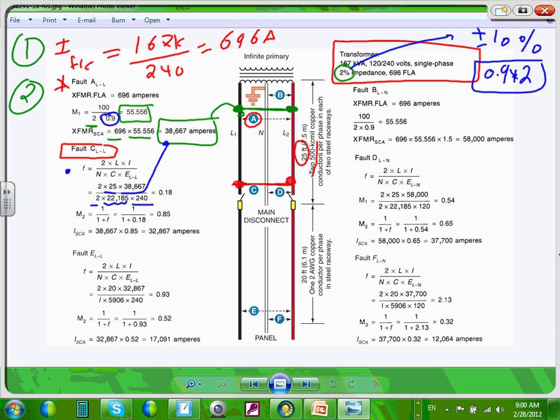If it's copper, you need to decide, is it 600 volt or higher than 600 volt? It's a 600 volt system, right? Less than 600 volt system, 240. And is it non-magnetic or steel conduit? Am I putting them in a steel conduit? Can you guys see where it says steel conduit here? Steel conduit. So do me a favor. What size conductor? 500. Can you go all the way to 500 under 600 volt steel? What's the number? 600 volt, 500 kcm steel conduit.